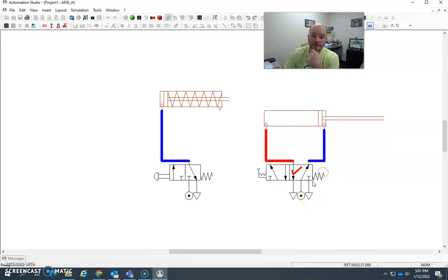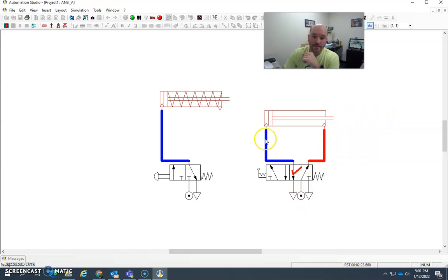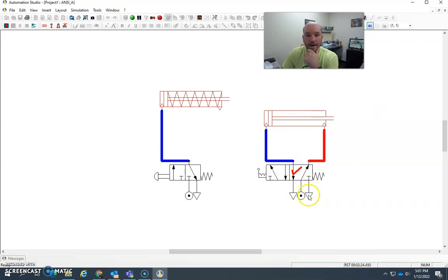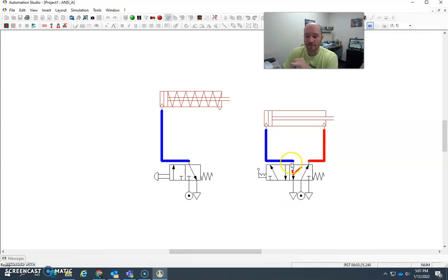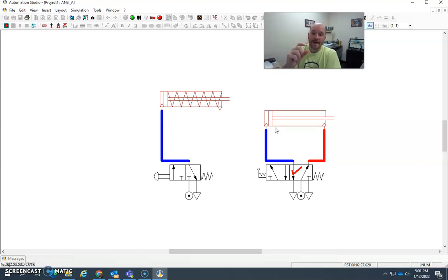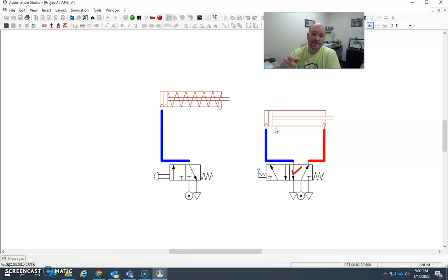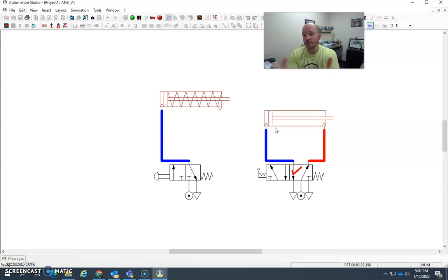And then when you go back to the other position, the pressure will retract that cylinder because air will flow through here into here, retracting the cylinder. This will flow down through here back to the exhaust. And this is why we have two exhaust ports, because each actuation port, A and B, need to be able to get that air out to atmosphere. And it's just cheaper to have a little muffler on there sometimes, or just let it spit out into the atmosphere than actually have it machined into the directional control valve like they would have on some larger systems, especially in the hydraulic systems.